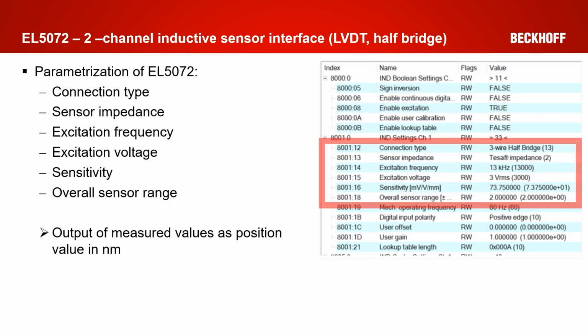In the next slides, I want to show you how you can parameterize the EL5072 correctly for your sensor. Here we need to focus mainly on 6 parameters: connection type, sensor impedance, excitation frequency, excitation voltage, sensitivity, and overall sensor range. If all the parameters are set in the correct way, the EL5072 will close all internal bridges by itself, make the corresponding connections, determine the correct amplification factors, and use the required calculation method. So at the end the output value becomes directly a position value measured in nanometers.